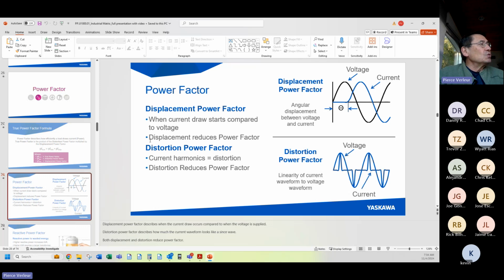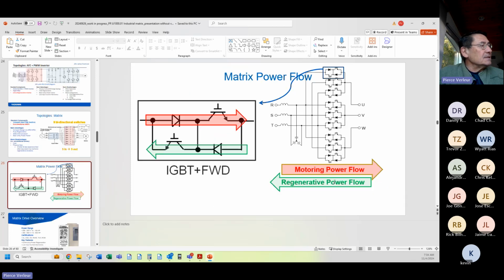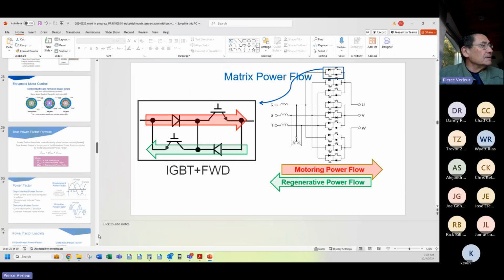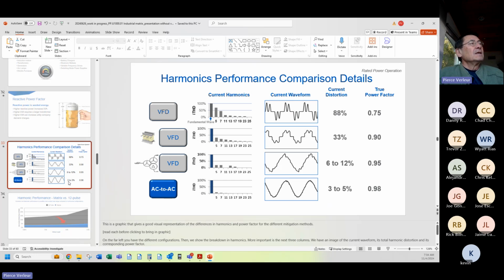To give you an idea of how much distortion is actually caused by the VFD, let's see if we can pull up a good diagram on that. There it is. Here's your distortion. We want the current distortion to be less than 5% so that the power factor can be up around 0.97, 0.98. This is just the standard VFD with the diode front end. And look at the amount of current distortion from those diodes. And the true power factor drops to 0.75, which is completely unacceptable.